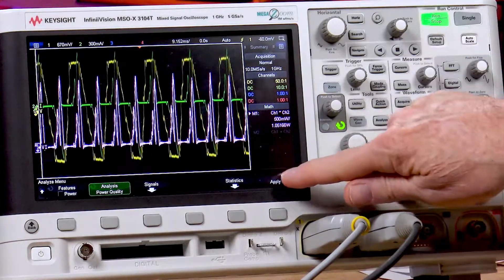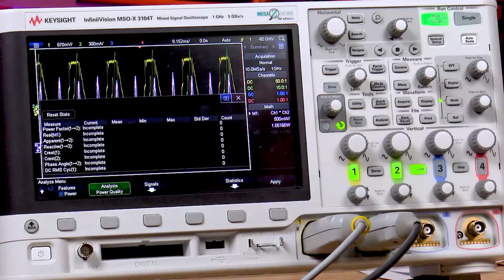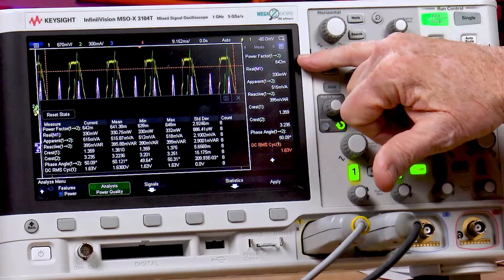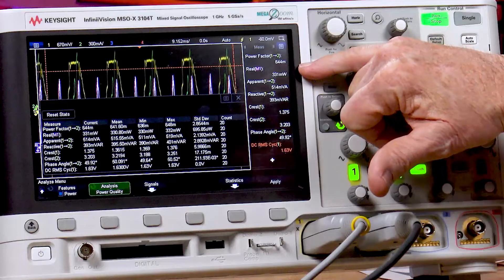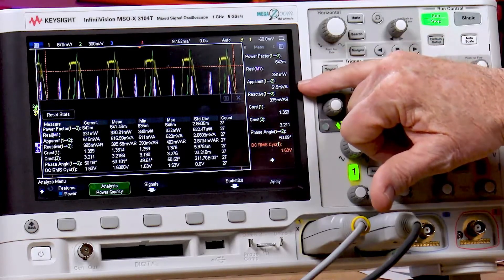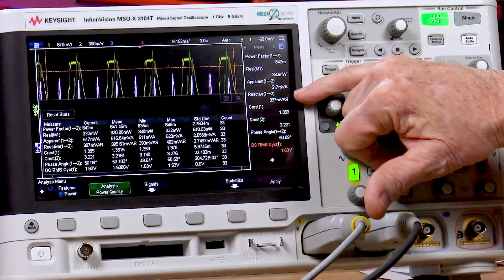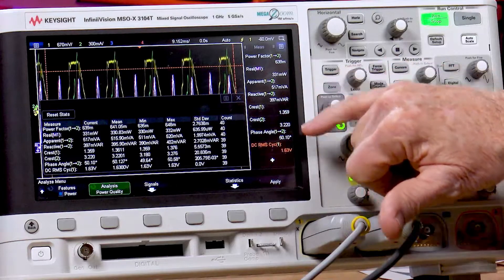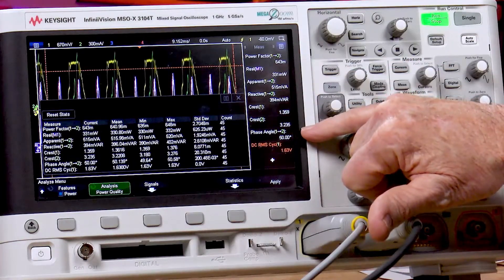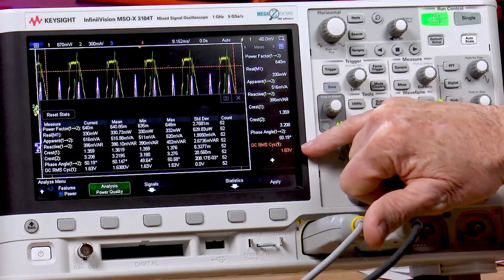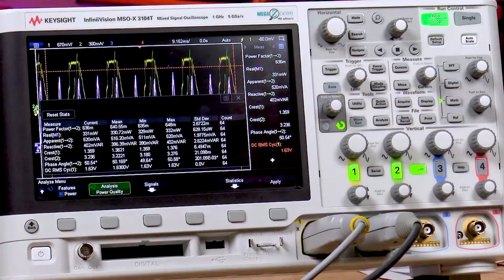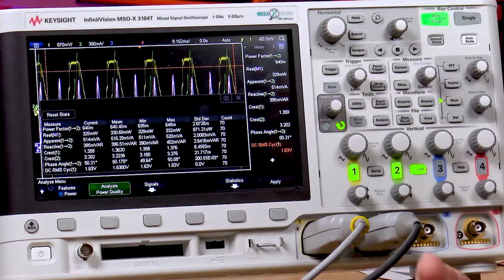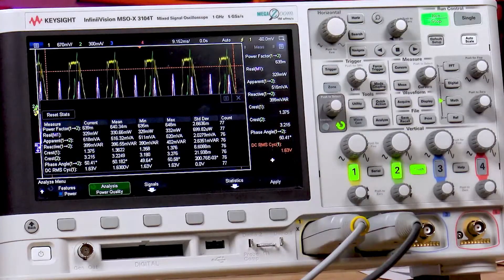Now if I select Apply, it automatically measures the power factor, real power in this case about 330 milliwatts, apparent power, reactive power, crest factor of voltage, crest factor of current, phase angle, and the RMS, which it says is only about 1.63 volts. There you see how easy it is to set up and measure power quality.